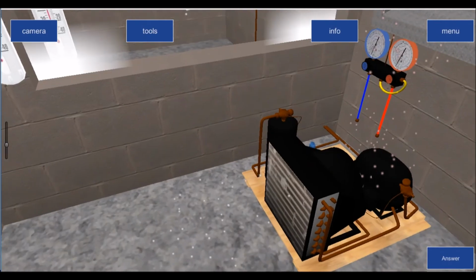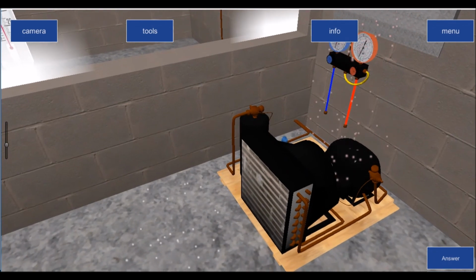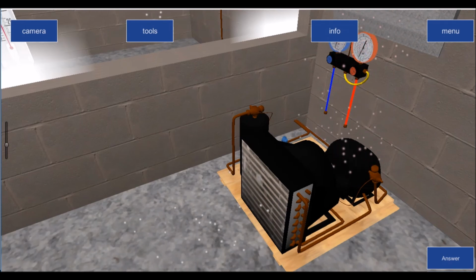Can you get? Sorry. So that was that. I would have thought that it would have got... You could have got with something slightly bigger than ambient temperature, you know, at the bottom of the condenser. Yeah. That doesn't matter. No, I hear what you're saying. Right. Okay. What happens here is you're going to have your 60, 70 degrees, so this is your de-superheating. And what happens here is you're going to have a slightly colder, because that's the condensing zone, and then what happens here is your subcooling zone, which is going to be colder again. So when you put your hand down along here, this will always be the coldest part.